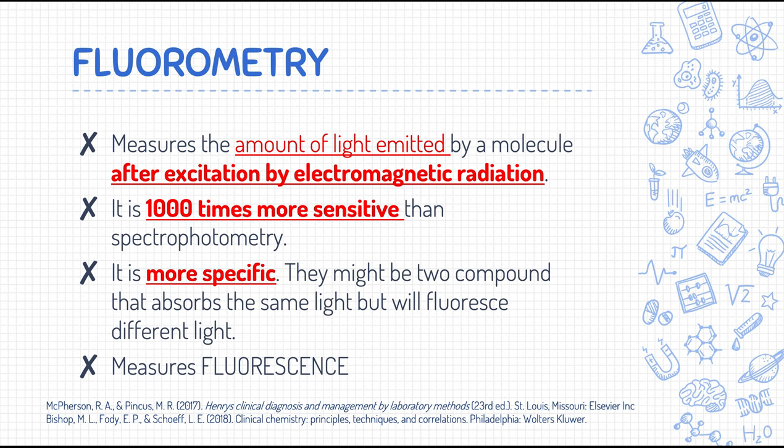The light source is a source of short-wavelength but high-energy light. The reason it must be short wavelength and high energy is because the goal is to excite the molecule. The most common light sources used are the mercury arc lamp and the xenon arc lamp. The key point to remember is that the light emitted by the light source is short wavelength with high energy, which is very important when we discuss fluorescence.